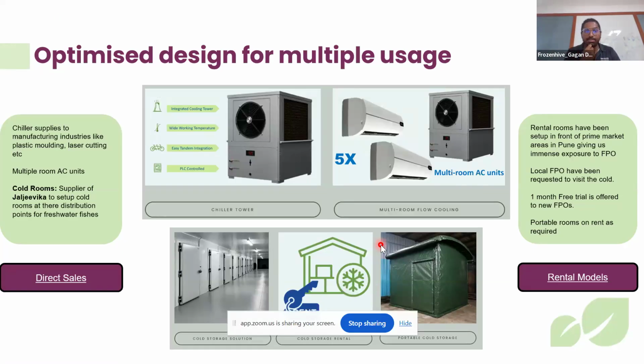So this architecture opens up a lot of opportunities for dealers. The unit could be pushed as a cold room unit, or for multi-room ACs. One of the major challenges of solar cold rooms is low volumes in the market, and low volumes inadvertently make any product inaccessible to the common consumer. So this design can also be used for office spaces with multiple ACs—instead of one single DX arrangement, you have a centralized cooling unit powering all the ACs, which can be expanded up to 5 units.